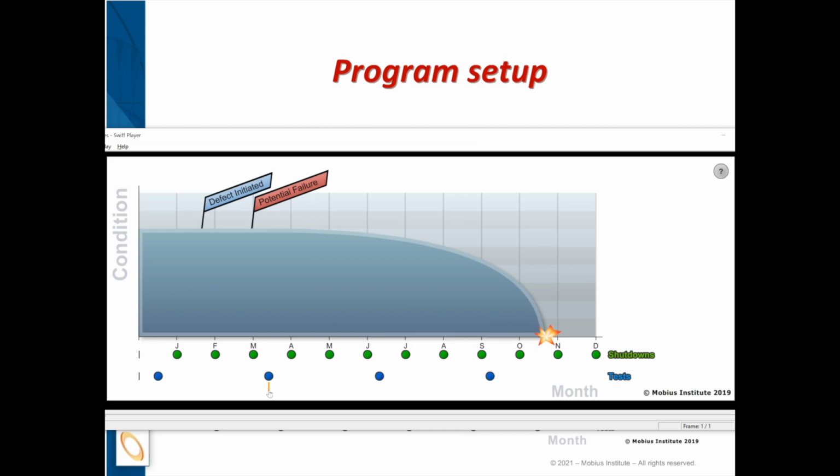At the same time, we have certain intervals when we can perform maintenance work, when there are planned shutdowns. That's the time of the next shutdown. You might be in a business that doesn't get to shut down very frequently. You need to understand that if I don't detect that problem before this shutdown, the next plant shutdown is outside our time window. On the other hand, you may have an organization that can have shutdowns very frequently, whether that's desirable or not is a whole other discussion. Well, it's not, but it means that I can do maintenance at any time.